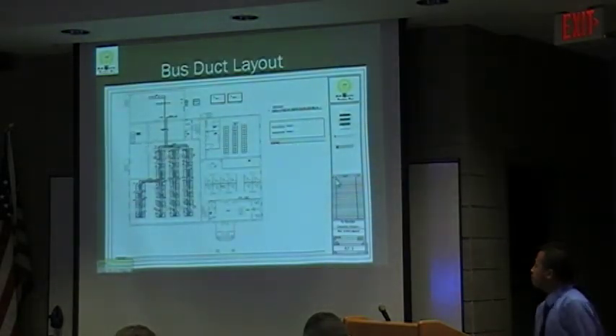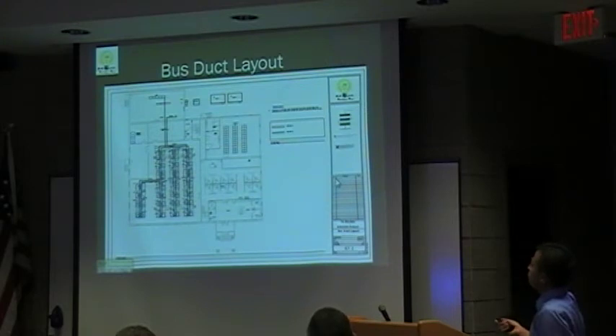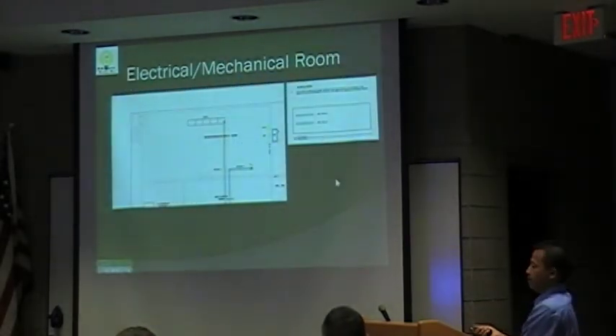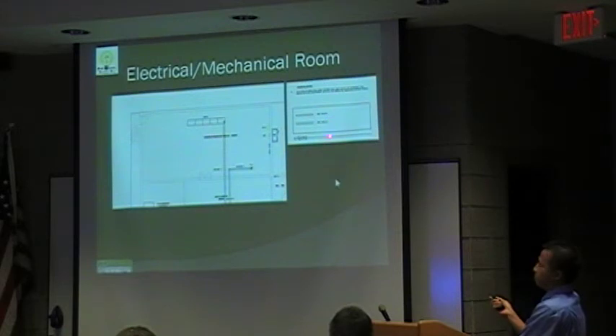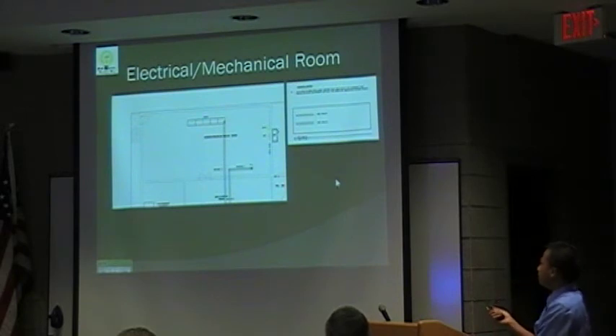Bus duct layout. This is the overview of our busway or bus duct layout. A little breakdown on each room. Here's our 480 volts and 208 volts. 480 is fed from the main switchgear, 4,000 amp. And 208 volt is fed from transformer 2.